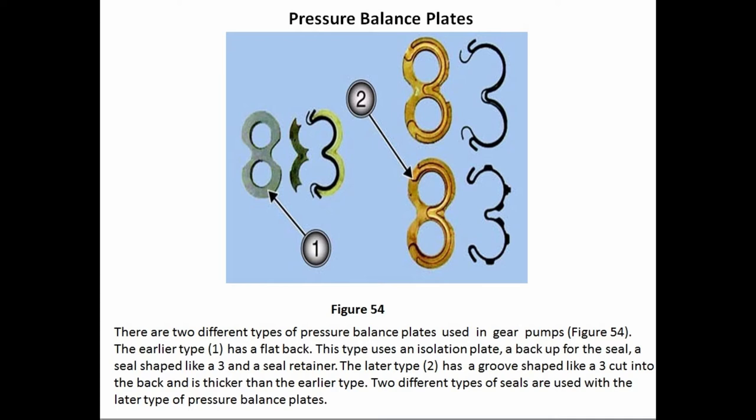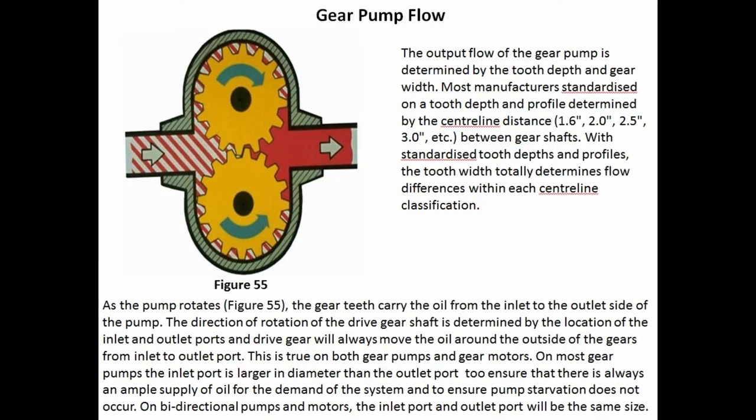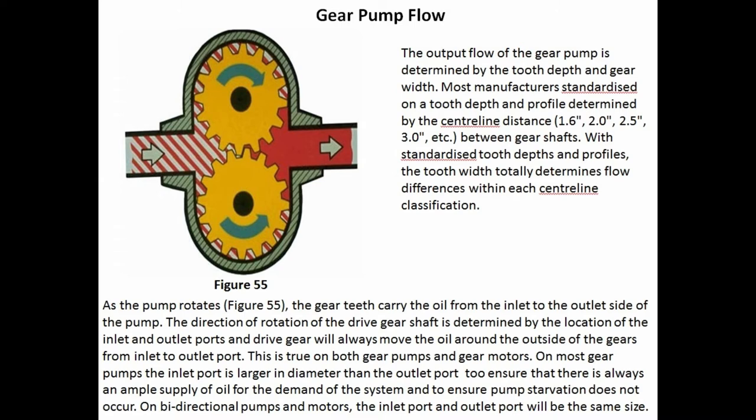Two different types of seals are used with the later type of pressure balance plates. The output flow of the gear pump is determined by the tooth depth and gear width. Most manufacturers standardize on a tooth depth and profile determined by the centerline distance (1.6, 2.0, 2.5, 3.0, etc.) between gear shafts. With standardized tooth depth and profiles, the tooth width totally determines flow differences within each centerline classification. As the pump rotates (Figure 55), the gear teeth carry oil from the inlet to the outlet side. The direction of rotation of the drive gear shaft is determined by the location of the inlet and outlet ports.